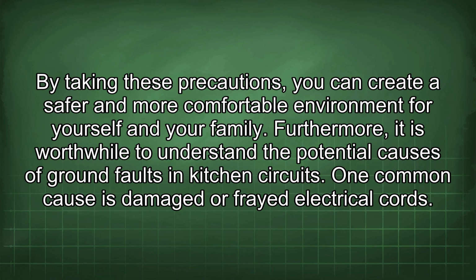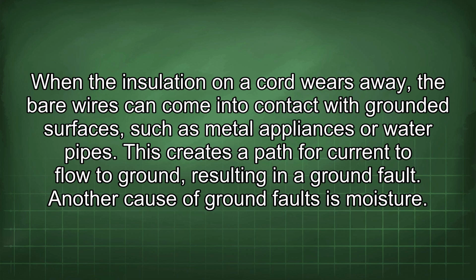Furthermore, it is worthwhile to understand the potential causes of ground faults in kitchen circuits. One common cause is damaged or frayed electrical cords. When the insulation on a cord wears away, the bare wires can come into contact with grounded surfaces such as metal appliances or water pipes. This creates a path for current to flow to ground, resulting in a ground fault.